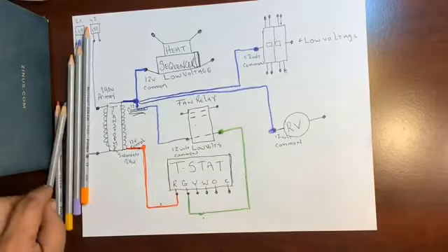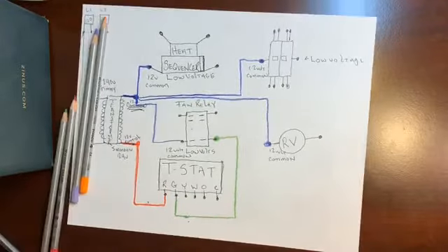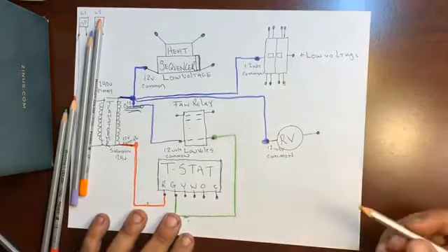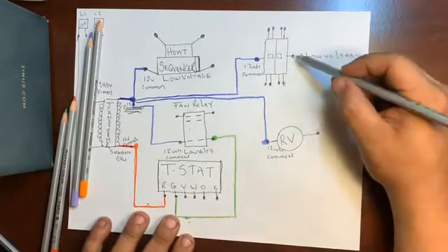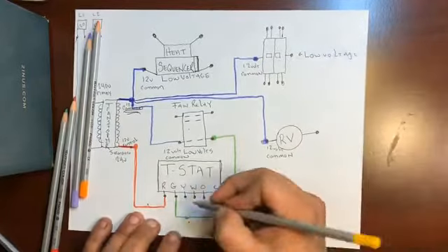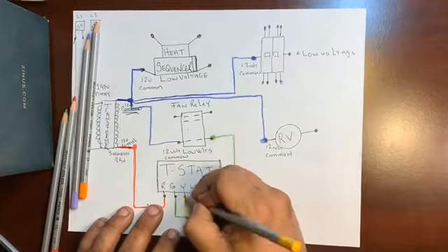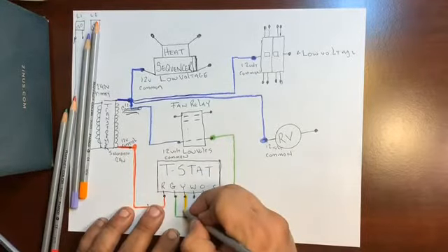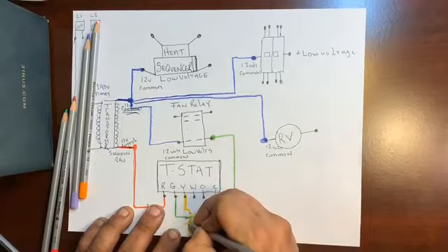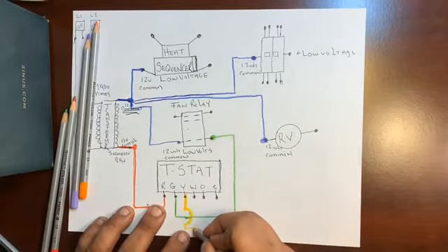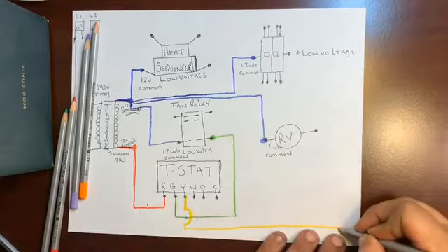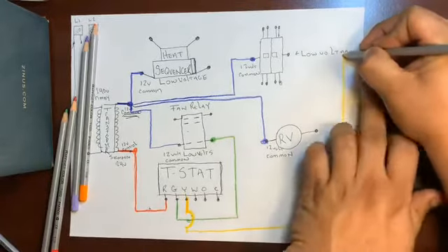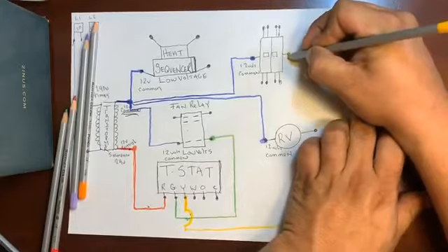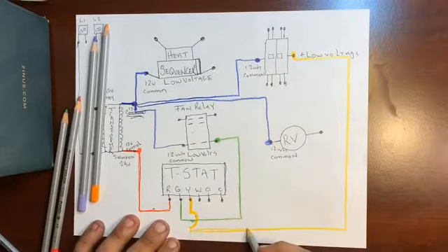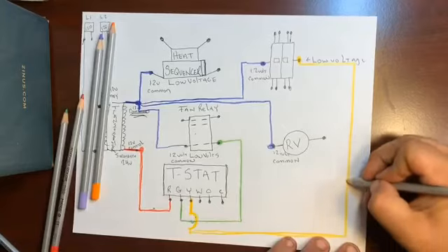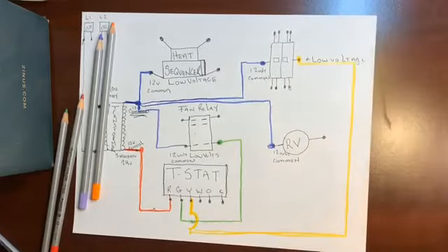What's our next one? We're going to go with yellow. Our compressor contactor, all the way out here. So we need to get 12 volts on the yellow. Compressor contactor gets the yellow. So yellow is going to drop down here. Don't forget our bridge, half moon bridge, to show that we're jumping a wire. Go all the way around, all the way up, all the way over. And now yellow is energizing the control side of our compressor contactor.